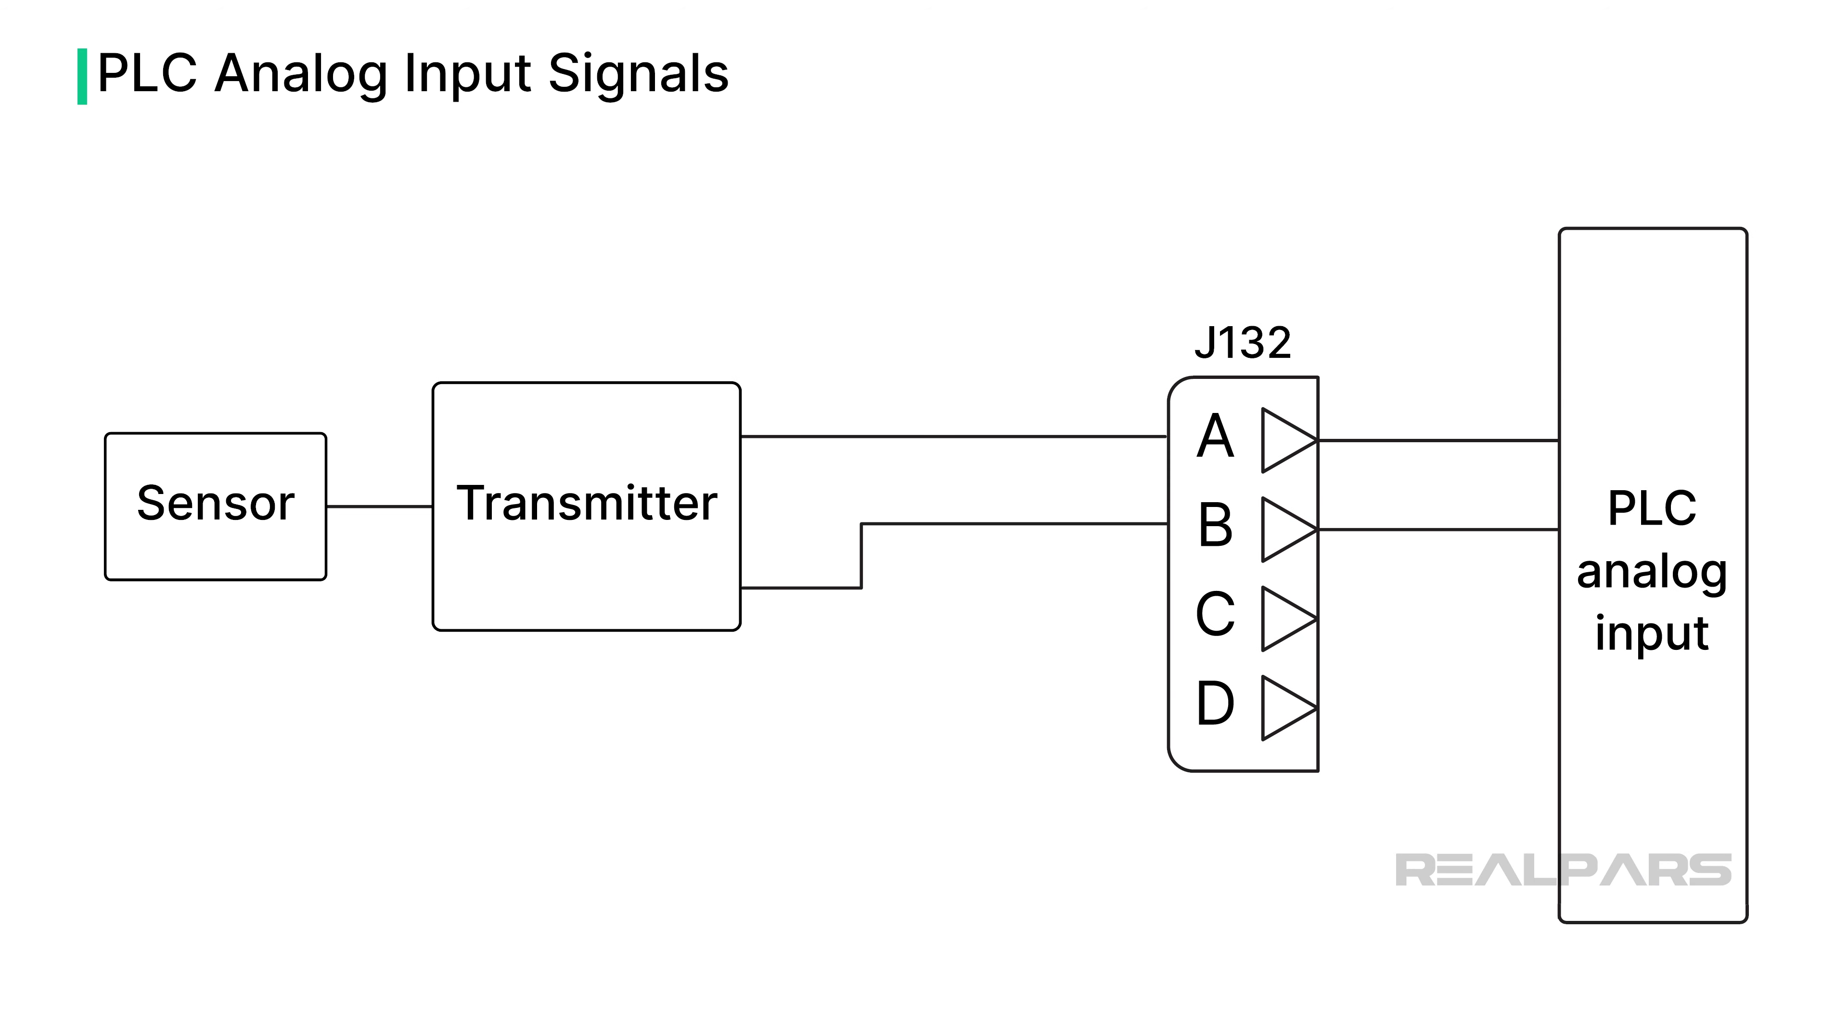Okay, let's look at PLC voltage and current analog input signals and where they originate. Typical voltage signals include 1 to 5 volts, 0 to 10 volts, and negative 10 to positive 10 volts. The most commonly used analog signal is 4 to 20 milliamps current.